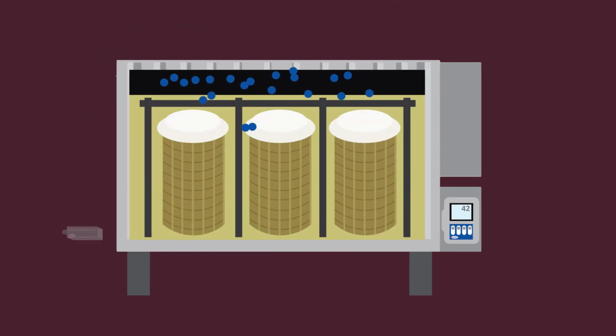With one design, sensors measure the hydrogen dissolved in the oil. Another design monitors hydrogen in the headspace. Hydrogen dispersion and saturation occurs more slowly in oil than it does in the gas phase. Hydrogen has a relatively low saturation in oil, and the dissolved gases will move into the headspace and disperse across the headspace faster than it will disperse throughout the oil.